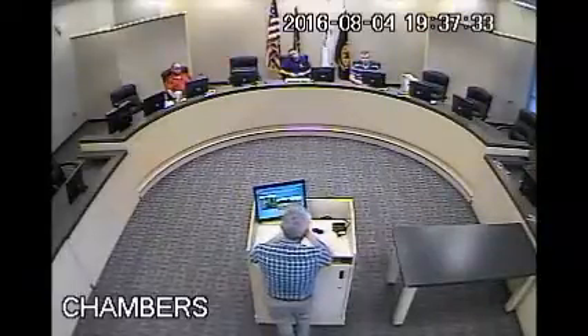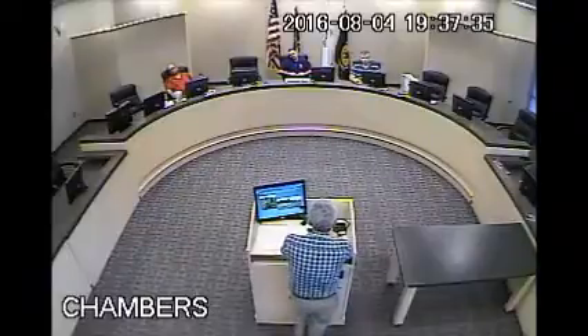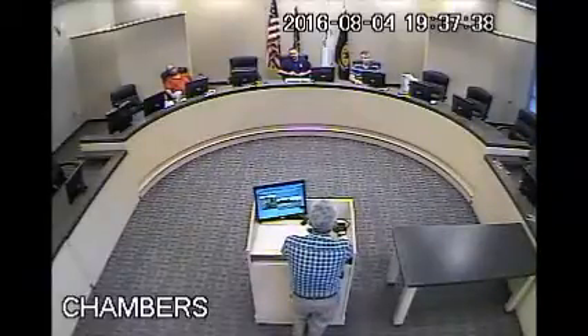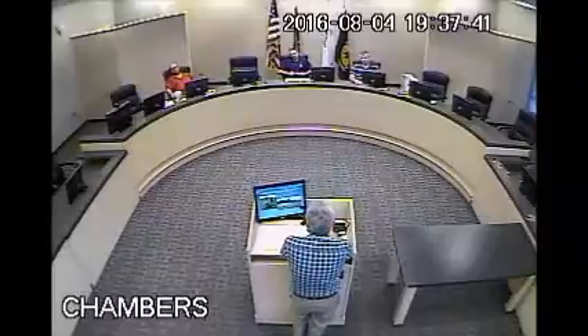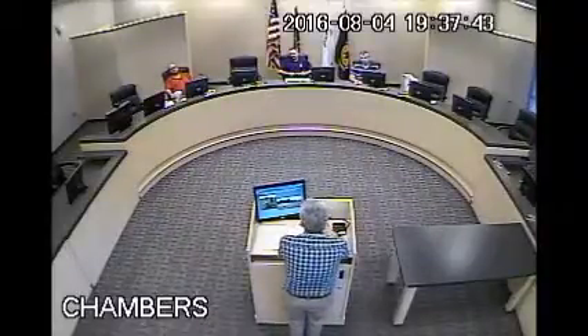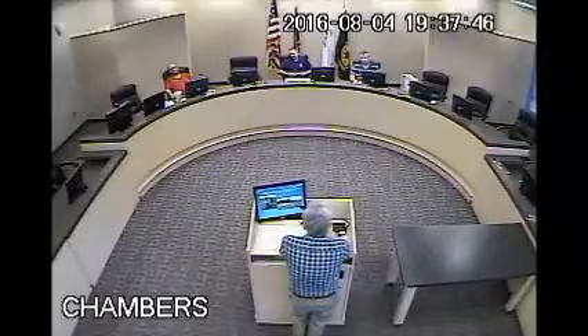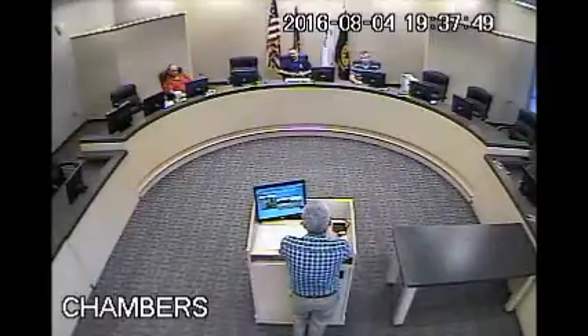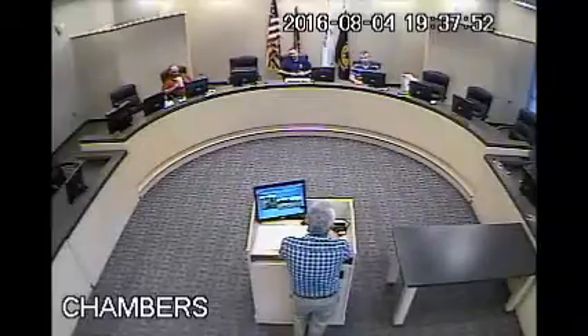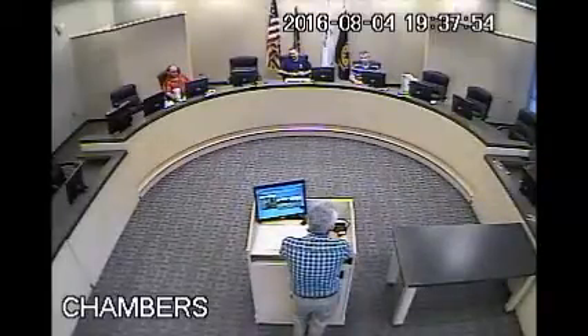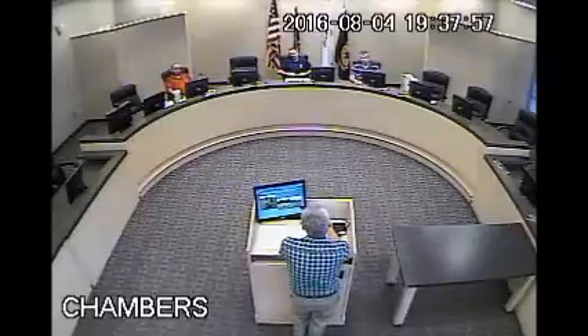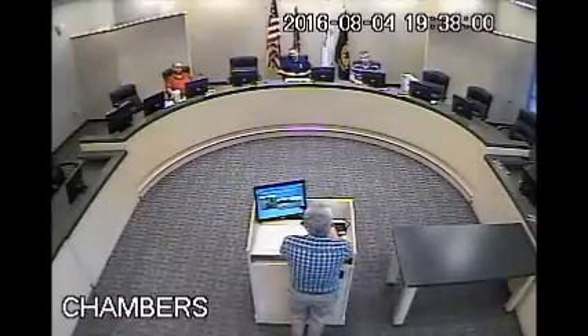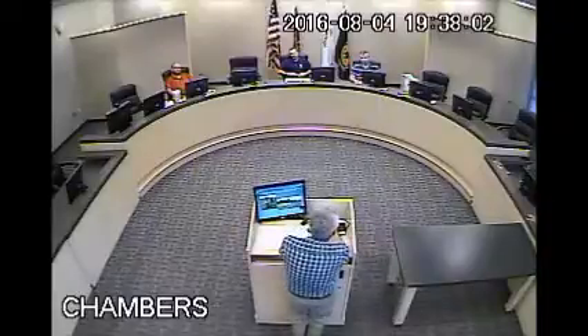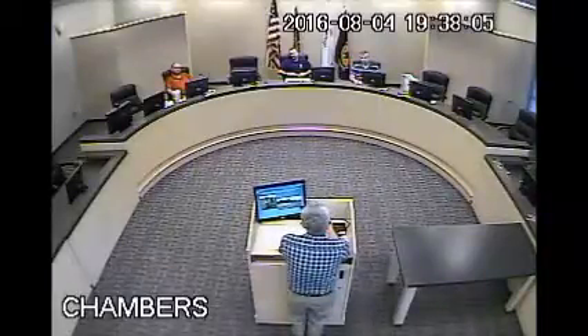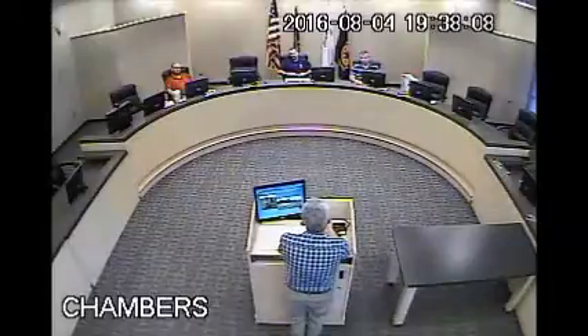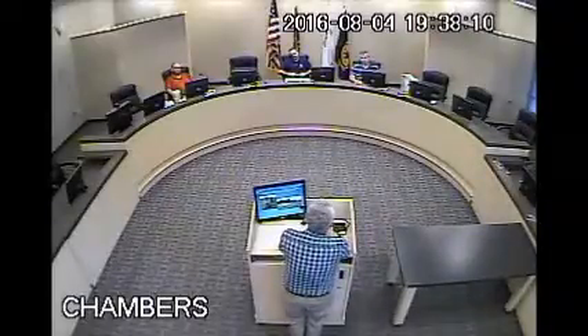And on the electric side, as I reported, or John reported, last month, we got the new transformer in. We got the new 161 kV breaker in. We got the two feeders coming off the T2 transformer about probably a month ago, probably less than a month ago. We energized T2 and put the two new feeders in service. Six hours after we did that, we got a differential on T2, so we tripped the circuit.